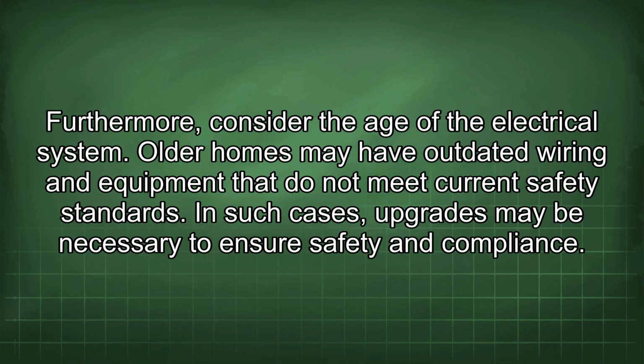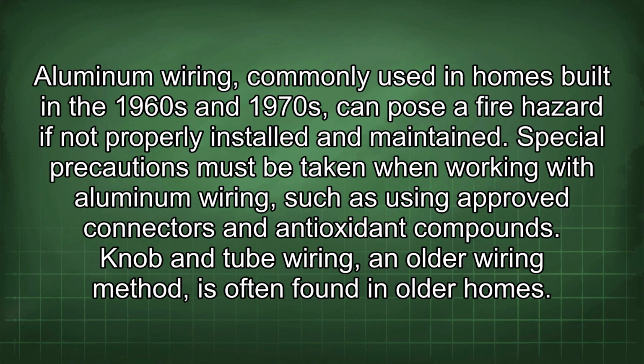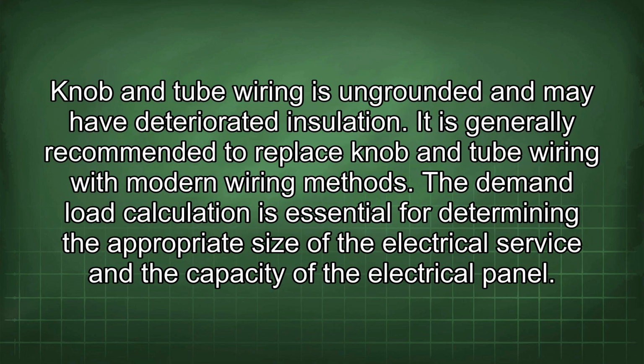Furthermore, consider the age of the electrical system. Older homes may have outdated wiring and equipment that do not meet current safety standards. In such cases, upgrades may be necessary to ensure safety and compliance. Aluminum wiring, commonly used in homes built in the 1960s and 1970s, can pose a fire hazard if not properly installed and maintained. Special precautions must be taken when working with aluminum wiring, such as using approved connectors and antioxidant compounds. Knob and tube wiring, an older wiring method, is often found in older homes. Knob and tube wiring is ungrounded and may have deteriorated insulation. It is generally recommended to replace knob and tube wiring with modern wiring methods.